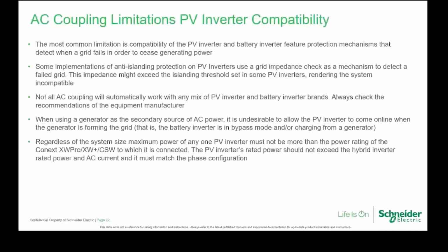Okay, some of the limitations we're going to strike when you do start doing AC coupling, basically it's to do with the compatibility of the inverters. Because you do use a frequency shift, some of them might not support a full frequency shift, and then they might not be fully compatible with the PV inverter and the battery inverters. Some implementations of anti-islanding protection on the PV inverters use a grid impedance, like I said before. So those types of inverters will not be compatible. Not all AC couplings will automatically work within the mix of PV inverters and battery inverter brands. So you basically need to do a bit of research, make sure that the inverter you're trying to use with the XW Plus, XW Pro, or SW is going to be compatible with frequency shift.